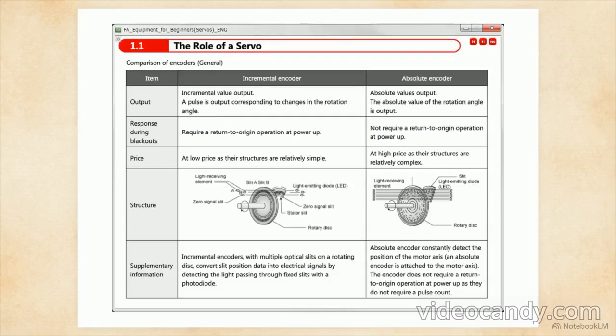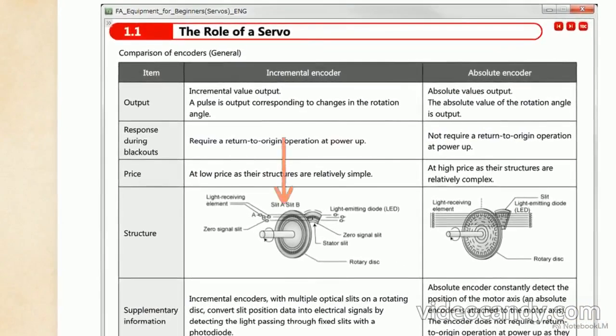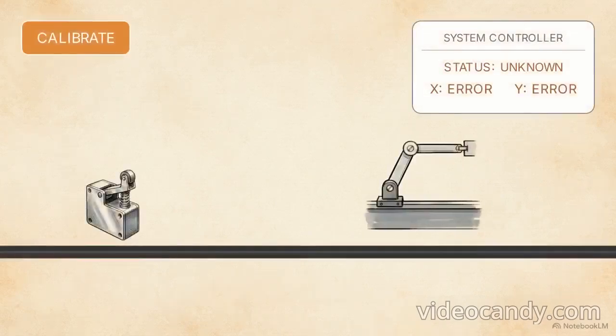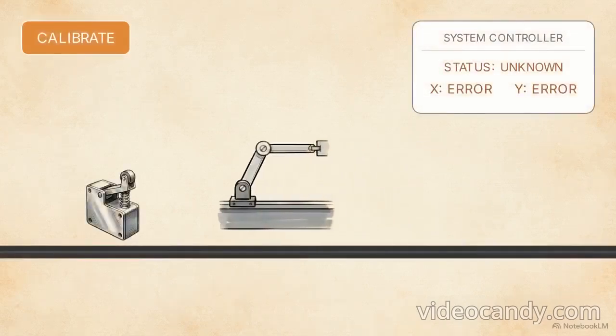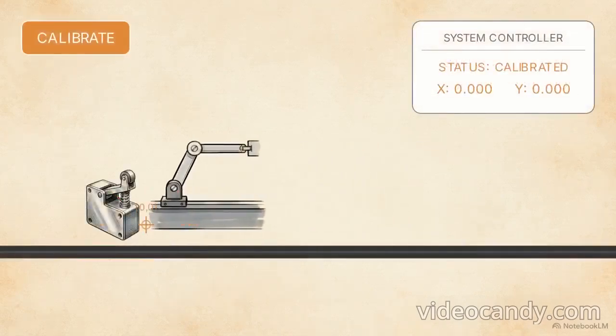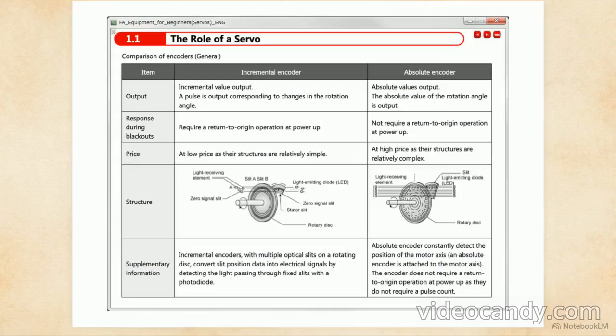This table provides a general comparison of encoders. Engineers choose between the two primary external feedback options listed here, incremental encoders and absolute encoders. Incremental encoders use multiple optical slits on a rotating disc to output speed pulses. Because they only count changes in the rotation angle, they require a manual return-to-origin operation upon power-up. A return-to-origin operation is a calibration process where the machine moves back to a known zero point so the controller can re-establish its coordinates. Contrast this with absolute encoders.